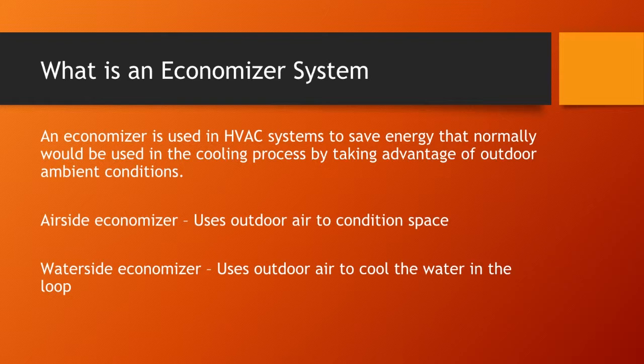An economizer system is used in HVAC systems to save energy, and it's going to use the outdoor air temperature to cool your building. And there's two different types. You got the air side economizer, that's using outdoor air, and it's just bringing it straight into your building. If it's cooler out than your indoor temperature, that's what you're going to use. Water side economizer, it's also going to use the outdoor air, but it's going to use that to cool your water for your chilled water loop instead of using the refrigeration cycle. It's going to save you some energy and only have to use pumps instead of compressors.